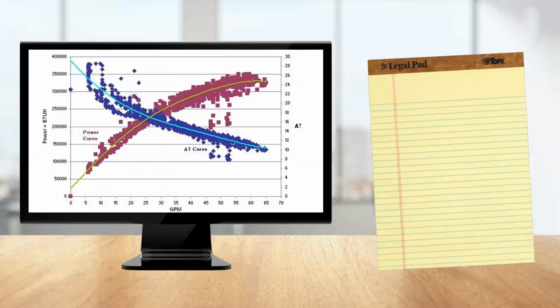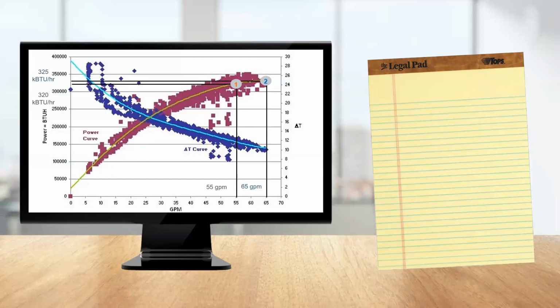So this right here is real-life data collected from an energy valve installed at MIT. It shows the diminishing return of BTUs as flow reached 55 GPM. But let's look at two potential operating points and their energy impact. Point one, we're achieving 320,000 BTUs at 55 GPM. Point two is 325,000 BTUs at 65 GPM.